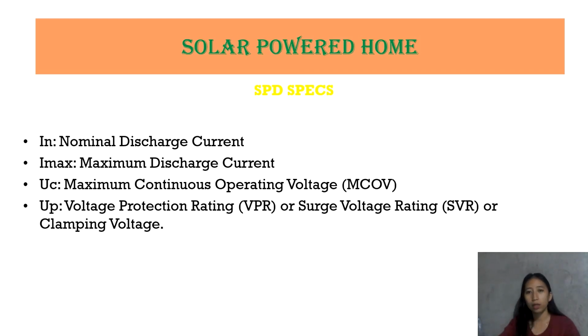So, what are the SPD specs natin? So, IN is nominal discharge current. Imax is maximum discharge current. Sa UC naman natin is maximum continuous operating voltage or the MCOV. So, UP is voltage protection rating or VPR or surge voltage rating or the clamping voltage.